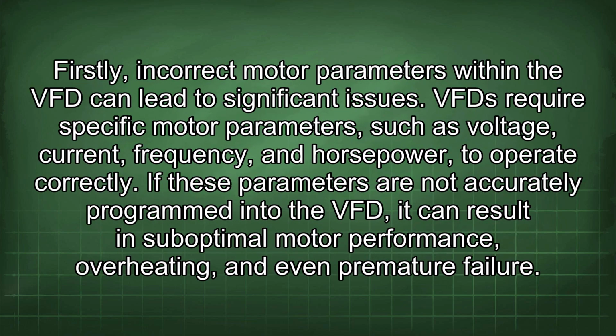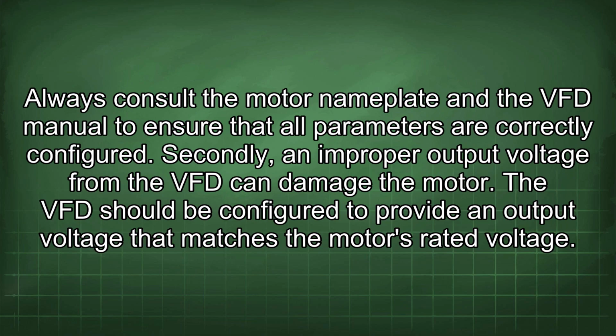Firstly, incorrect motor parameters within the VFD can lead to significant issues. A VFD requires specific motor parameters, such as voltage, current, frequency, and horsepower, to operate correctly. If these parameters are not accurately programmed into the VFD, it can result in suboptimal motor performance, overheating, and even premature failure. Always consult the motor nameplate and the VFD manual to ensure that all parameters are correctly configured.